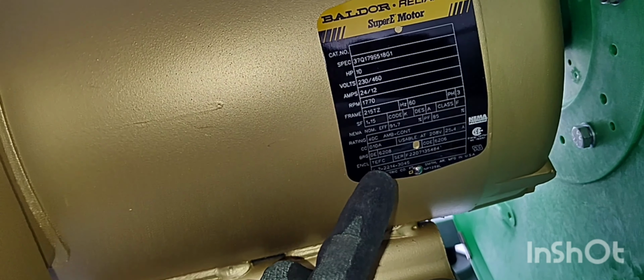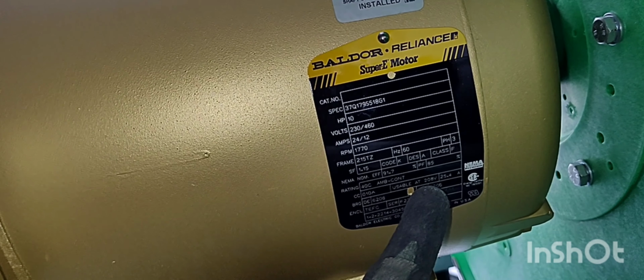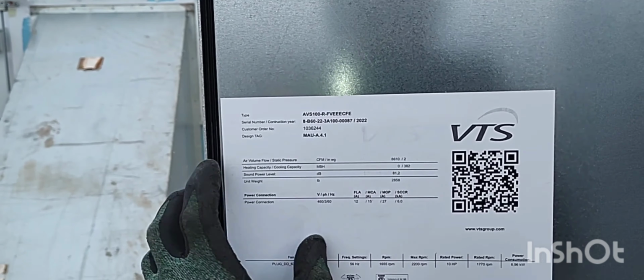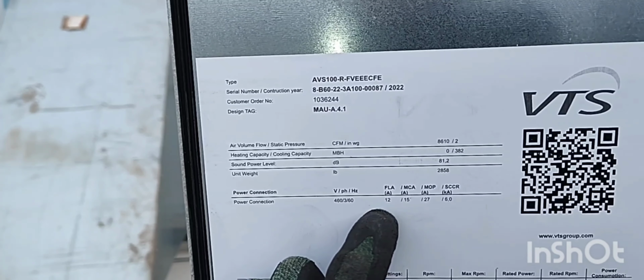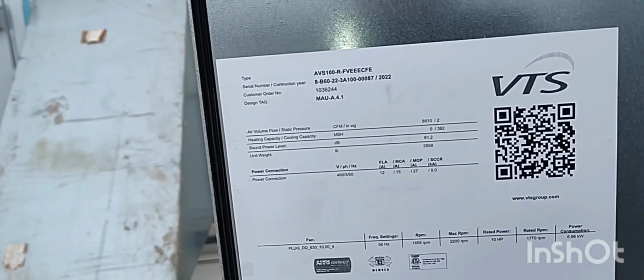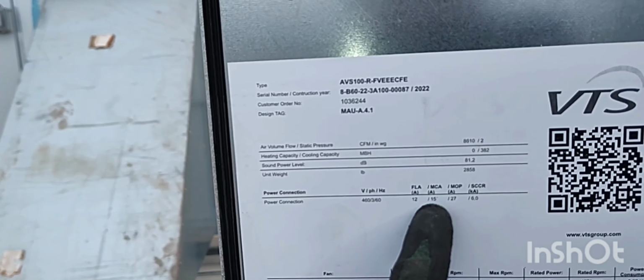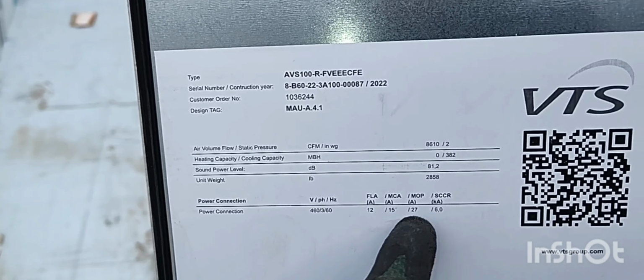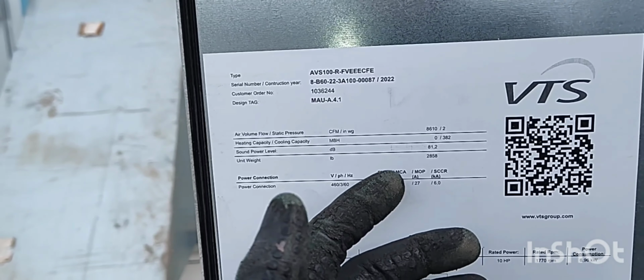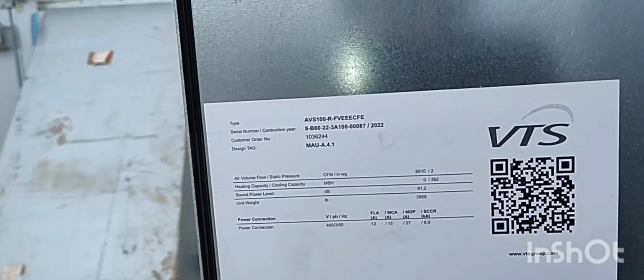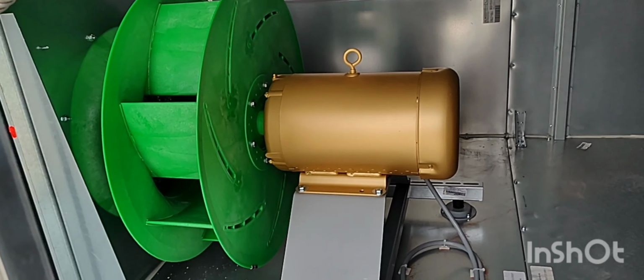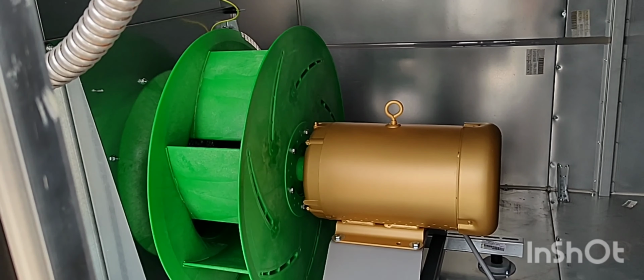Now I believe it says, yeah, usable at 208 volts. So there's also tap options for that. And then we can take those values into the classroom and size our conductors. On this nameplate right here, full load amperage 12, so we automatically know, line that up with the 460. That's what we're using. Max circuit ampacity is 15, max overcurrent protection 27, so we just round that up to 30 for the size up rule. But for sizing our conductors, we're going to take that nameplate and go in the code book and figure out exactly what we need.